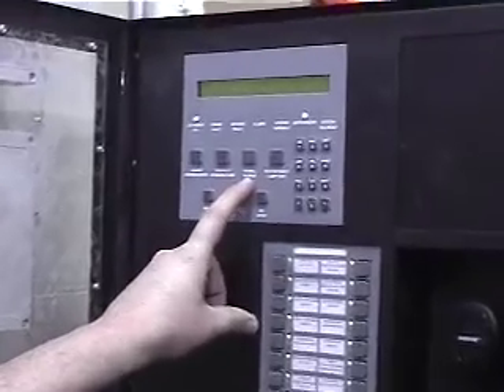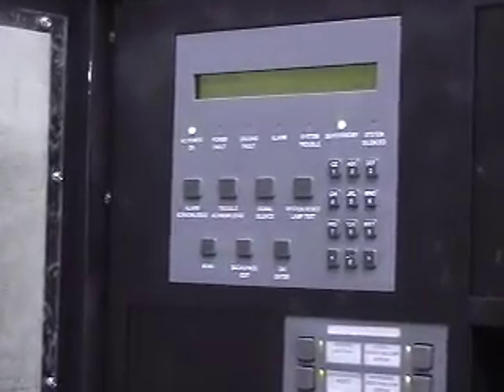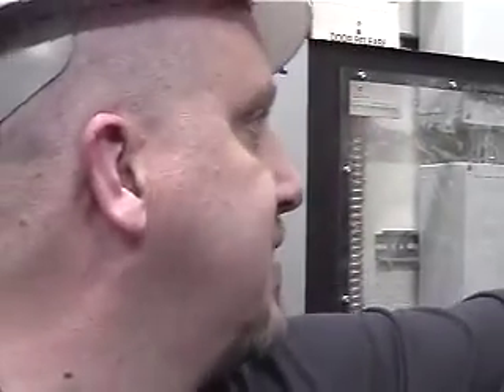When you go on alarm, press the silence. That silences the speakers, but your strobes will go until you reset, and that's just how the state likes it. I know they had it in NFPA for a while, but they took it out, but the state kept it in their code because they like to be able to silence the alarm to not bug the fire department inside, but still let people know that there's an alarm. So your strobes will keep going until you reset, or you bypass them if you need to.